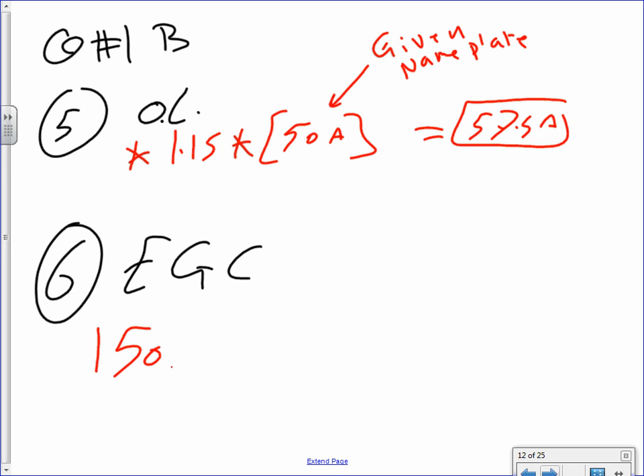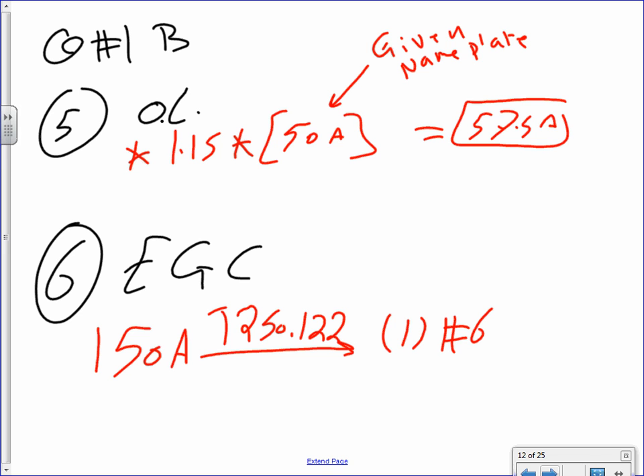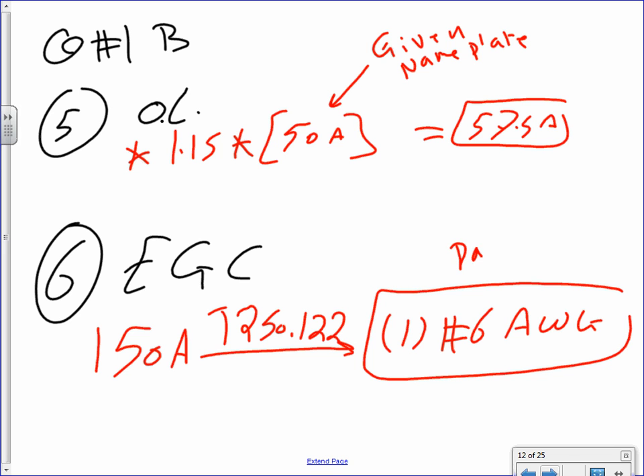The last thing, guys, is the equipment grounding conductor. You take the 150 amp circuit breaker, take it to table 250.122, and that will get you one conductor, number 6 AWG, and that will be part of your NMB cable.